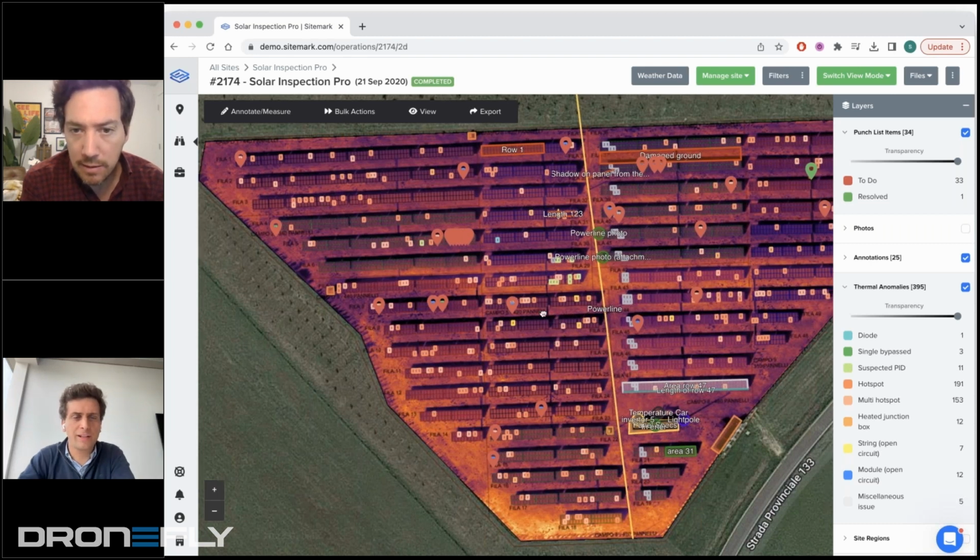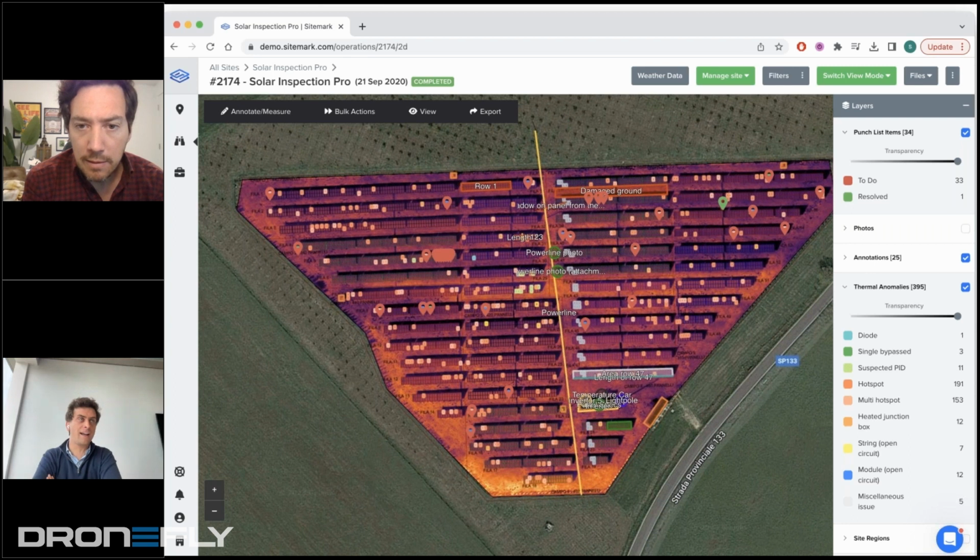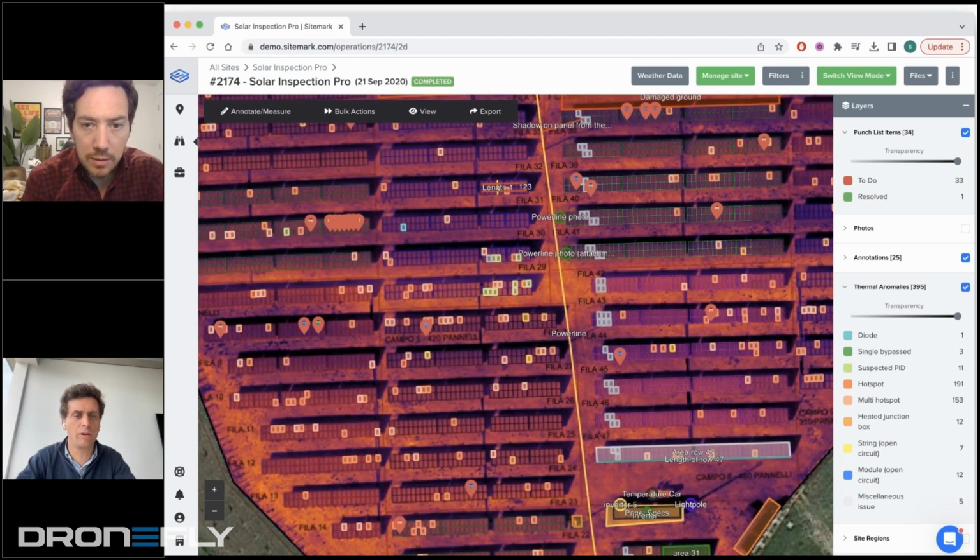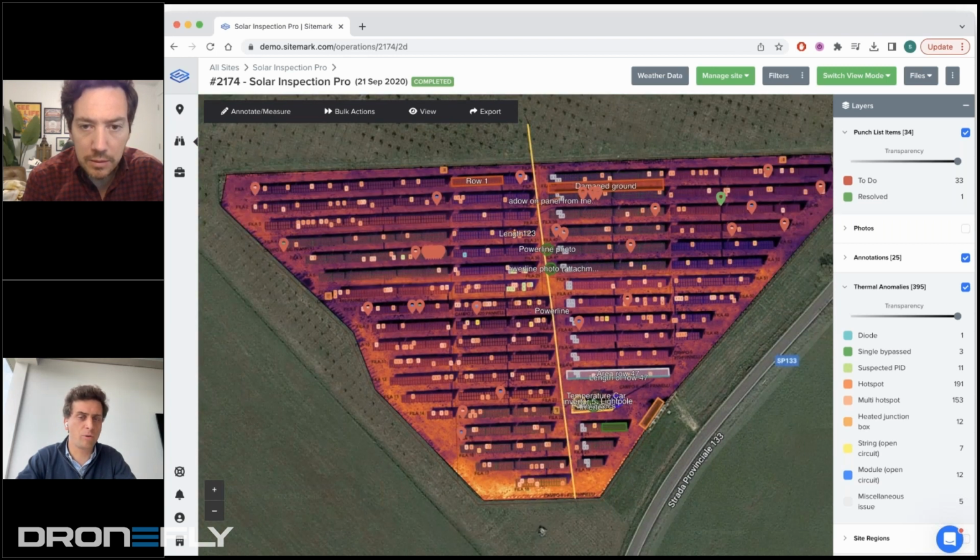And the reason for that is that's what the IEC recommends, so the official standard. But on top of that, also anomalies don't change that fast. And most of our customers do have a monitoring system, which is going to send them an alarm if a big part of the site breaks down, basically. The monitoring systems are really good at ensuring availability, making sure that all the hardware is available. We are there to do performance, but you're not going to send a technician 5 times a year to your site anyway. So if you're doing a thermography every year and you're sending a technician after the thermography and he knows exactly what to go and look for, we think that's a very efficient way of working.